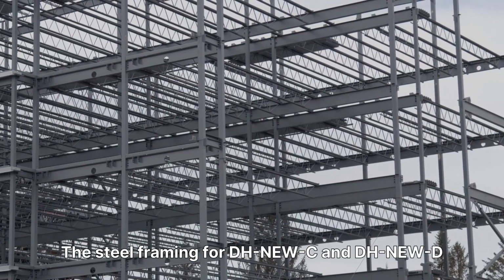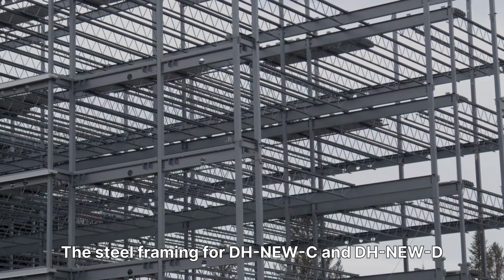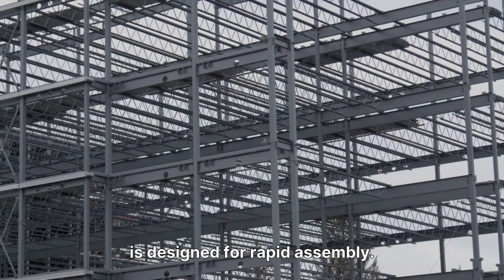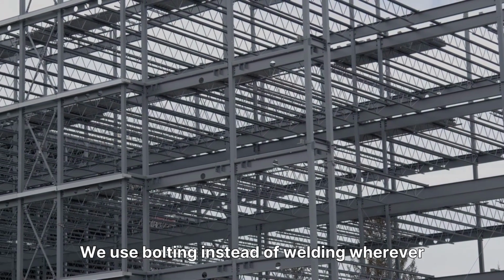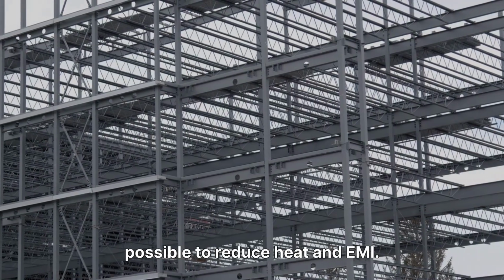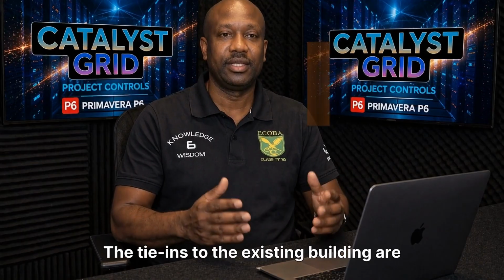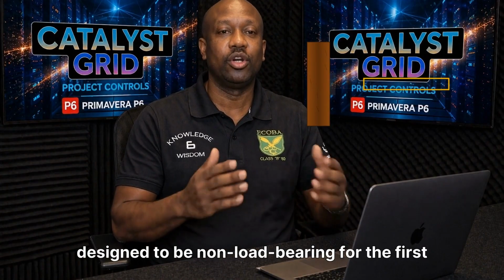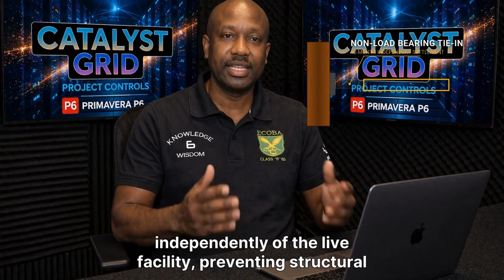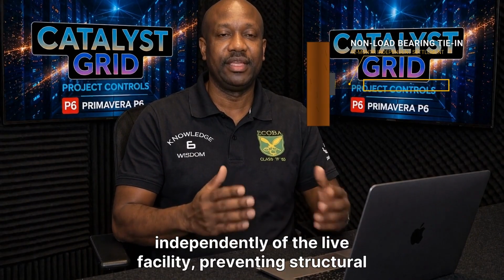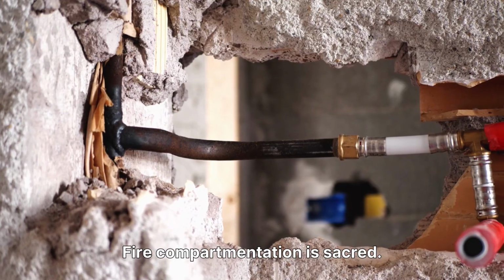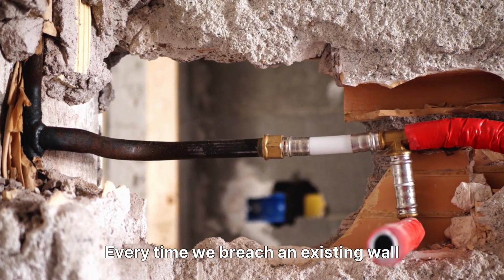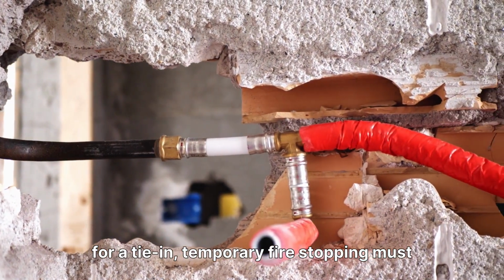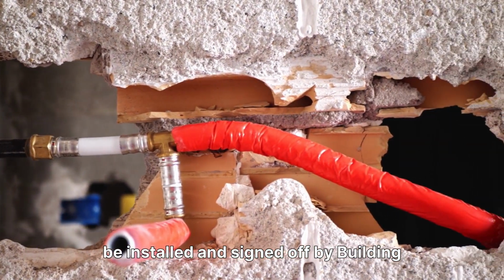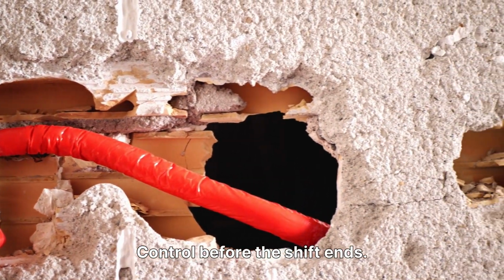The steel framing for DH New C and DH New D is designed for rapid assembly. We use bolting instead of welding wherever possible to reduce heat and EMI. The tie-ins to the existing building are designed to be non-load bearing for the first 12 months. This allows the new structure to settle independently of the live facility, preventing structural stress. Fire compartmentation is sacred. Every time we breach an existing wall for a tie-in, temporary fire stopping must be installed and signed off by building control before the shift ends.